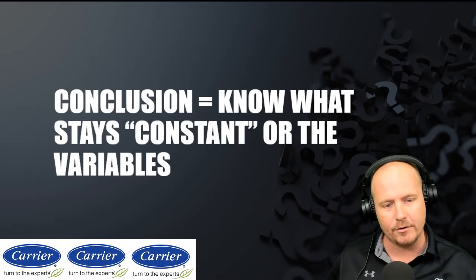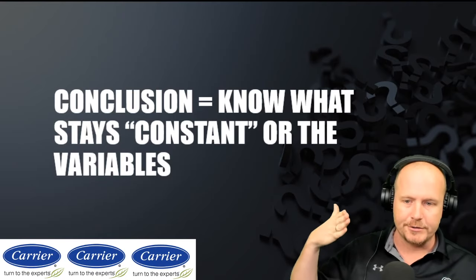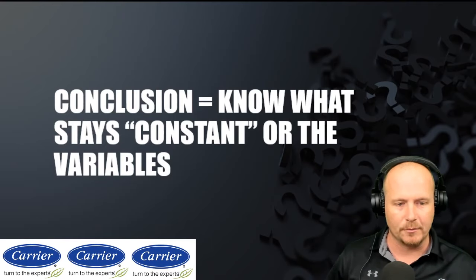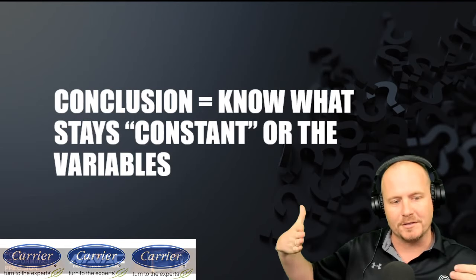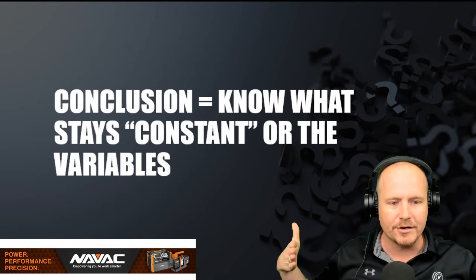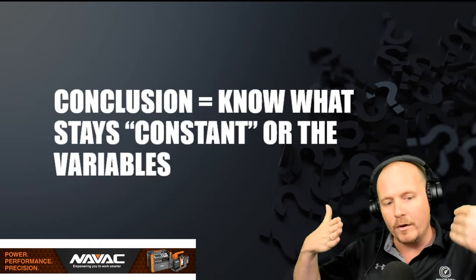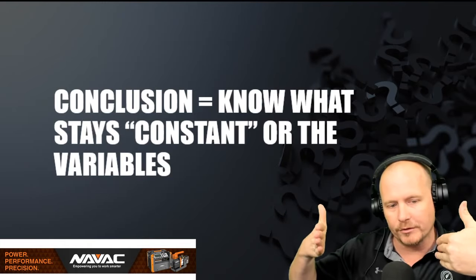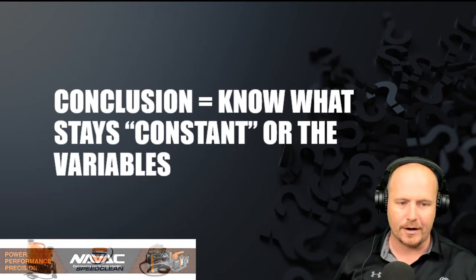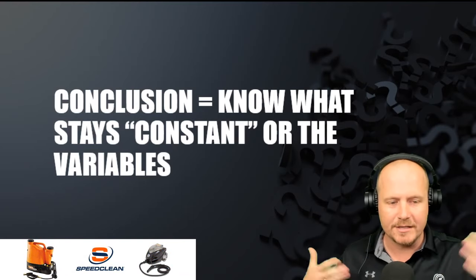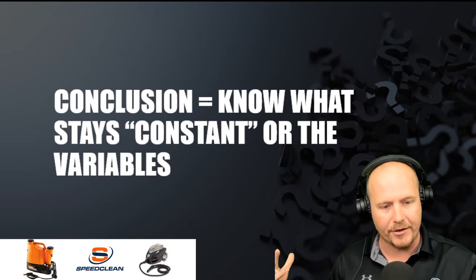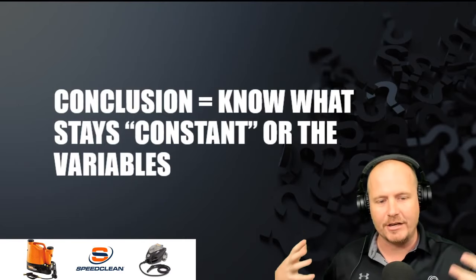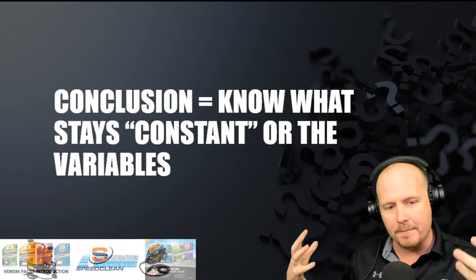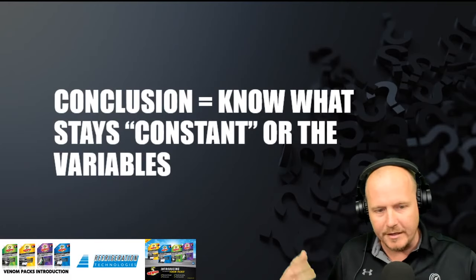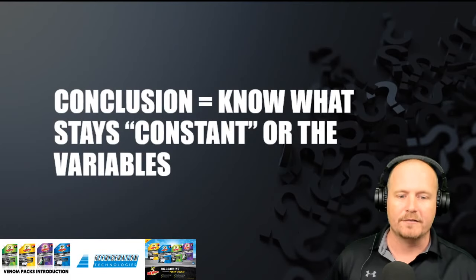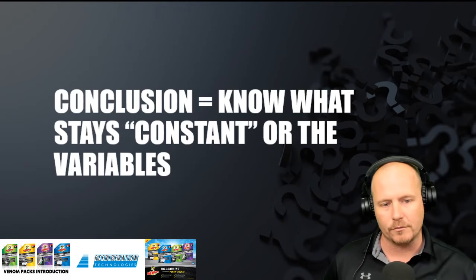You do the same thing, you dial back the input voltage to a variable frequency drive, and what does it do? It can control its output, so it has a wider range of acceptability. If you back off the voltage slightly heading into a variable frequency drive or into an ECM, you definitely will see an increase in current because you have something actively changing the wattage, actively impacting the output of the motor. So it really depends what type of device you're working on as to what the result will be.